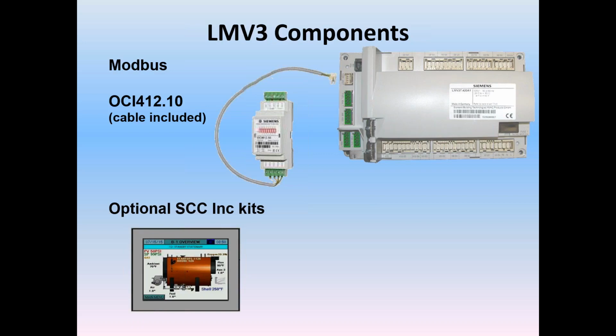So instead of just the AZL, you have a nice HMI. Or any other Modbus device that you have, such as your building management system, a master lead lag panel, or any other Modbus device that you see fit. It just adds the Modbus capabilities to the standard LMV3.